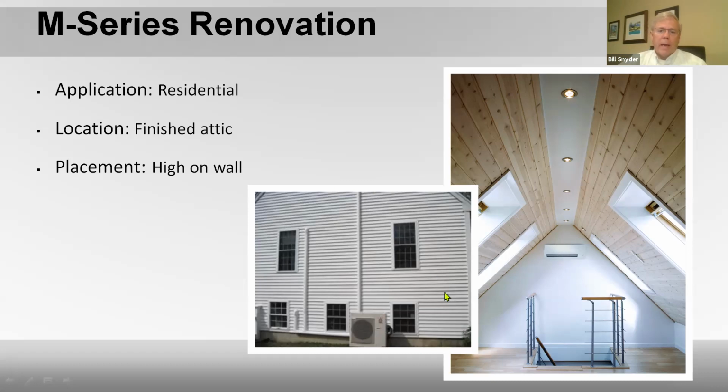So that's probably the only application. This appears to be the back of the house, so this is mounted here. You probably don't want the line hide running down the front of the house. Probably your only option is put that unit here, or you could put one of those low wall units down here. This could be a challenge to service and change the filter, being there's a stairway here. You have to put a ladder coming up here, or lay something across here to get up and service it. So in this application, I don't know what else you'd use except for maybe one of those low wall units.